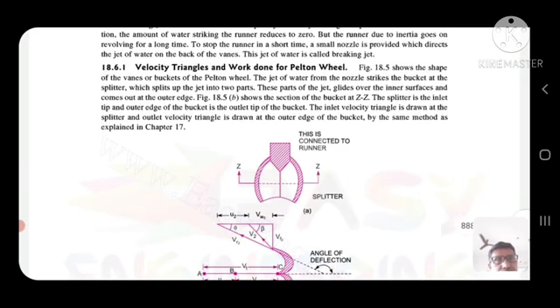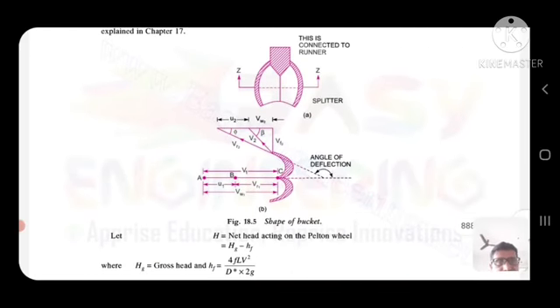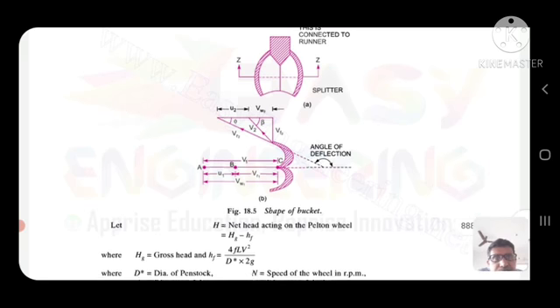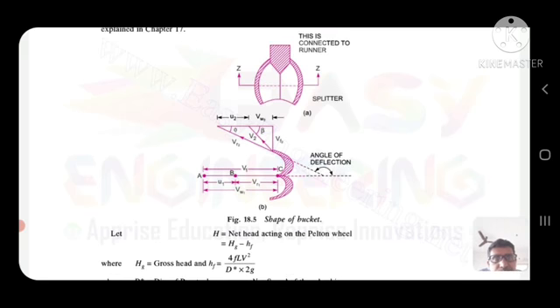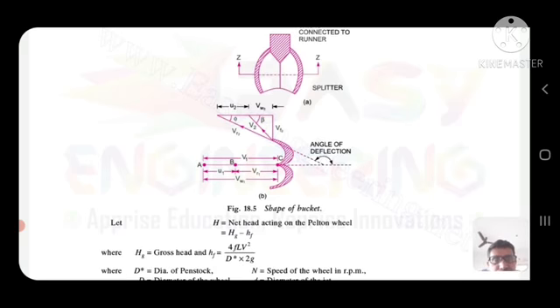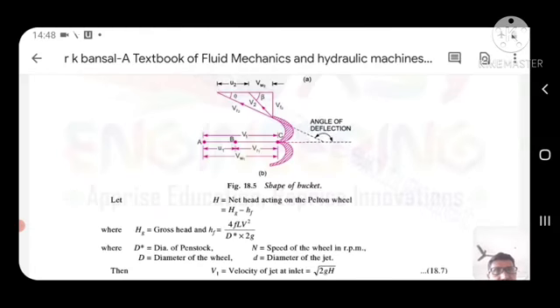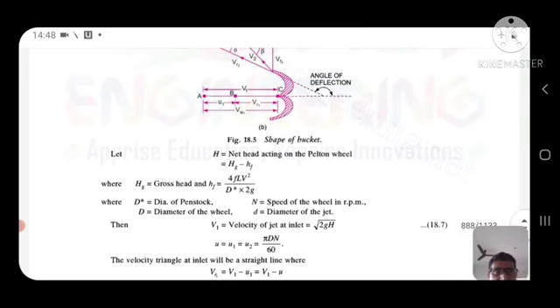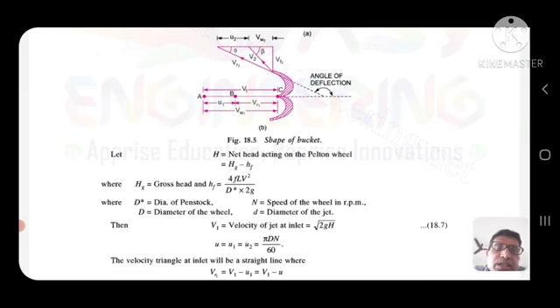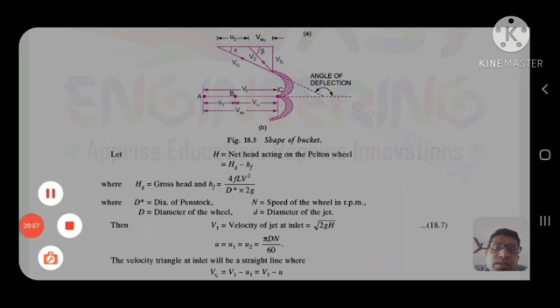Velocity triangle and work done of a Pelton wheel: the inlet velocity triangle and exit velocity triangle are shown. The net head acting on a Pelton wheel is H = Hg − HF, where Hg is the gross head and HF = 4fLV²/2gD. D is the diameter of the penstock, n is the speed of the wheel in RPM, D is the diameter of the wheel, and d is the diameter of the jet. The jet velocity V1 = √(2gH), and the peripheral velocity U = U1 = U2 = πDN/60.